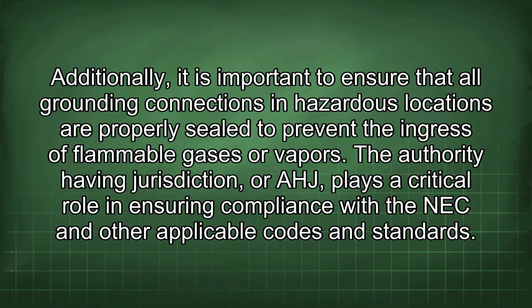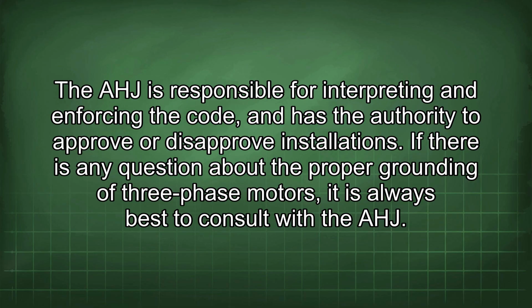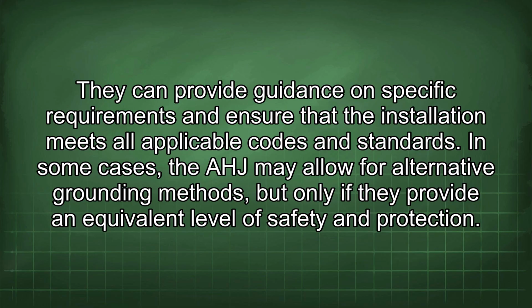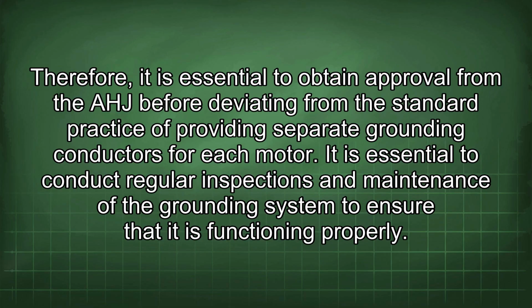The authority having jurisdiction, or AHJ, plays a critical role in ensuring compliance with the NEC and other applicable codes and standards. The AHJ is responsible for interpreting and enforcing the code and has the authority to approve or disapprove installations. If there is any question about the proper grounding of three-phase motors, it is always best to consult with the AHJ. They can provide guidance on specific requirements and ensure that the installation meets all applicable codes and standards. In some cases, the AHJ may allow for alternative grounding methods, but only if they provide an equivalent level of safety and protection. Therefore, it is essential to obtain approval from the AHJ before deviating from the standard practice of providing separate grounding conductors for each motor.